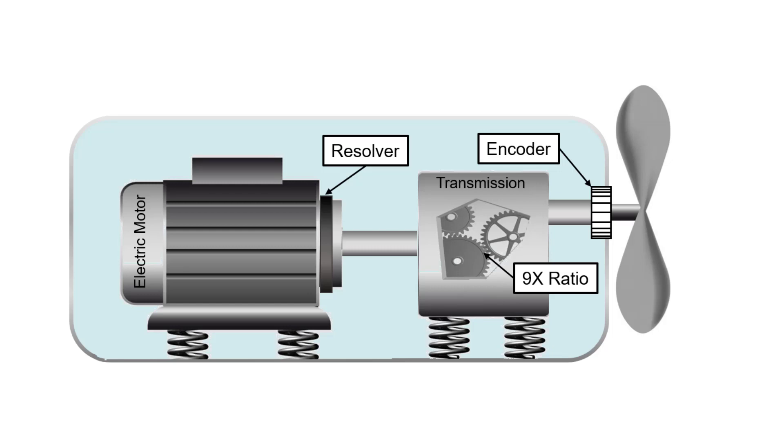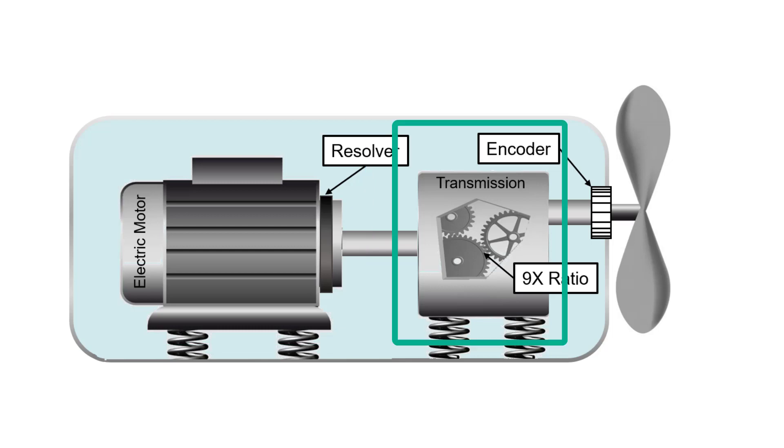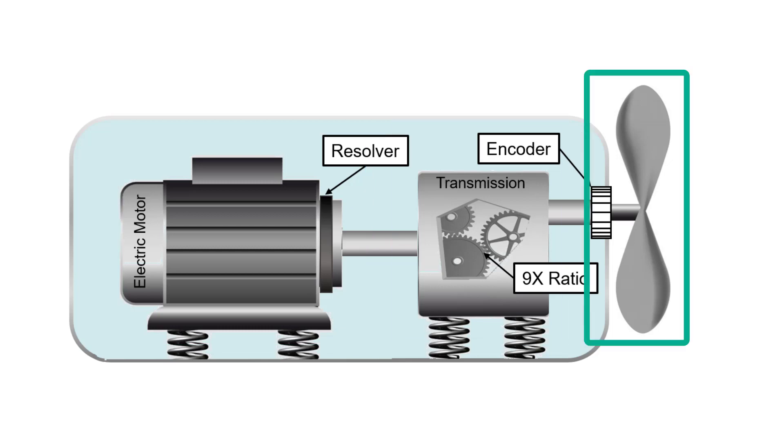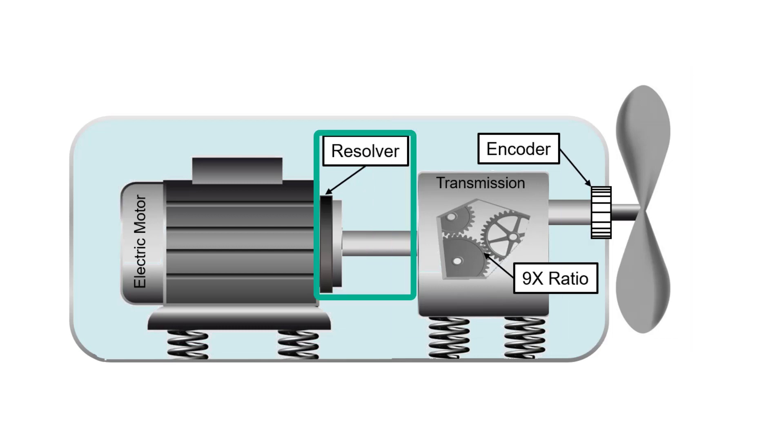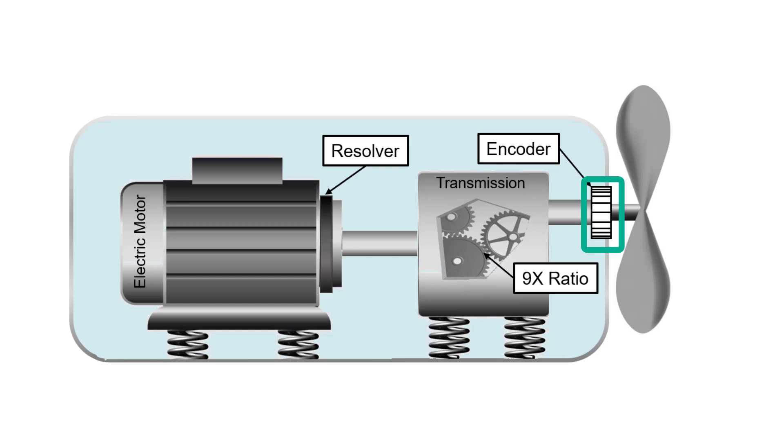Here we have a rotating system driven by an electric motor through a transmission to a final drive. On the electric motor there's a resolver which determines the angular position of the electric motor. On the final drive we have an encoder which can also determine the angular position. What we want to do is determine the angular difference between these two positions to troubleshoot an unwanted vibration that occurs during the run-up and run-down of this rotating system.